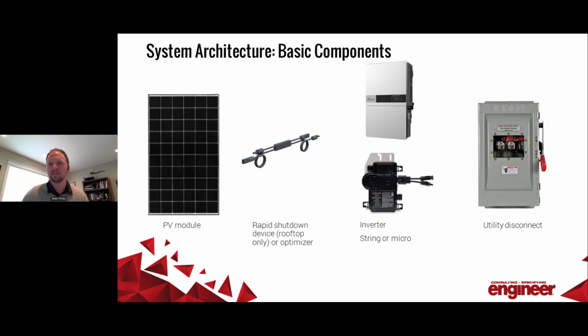The basic pieces of any solar system are shown here. We'll start with our PV modules. We're all probably familiar with those. On any commercial building, we'll probably have hundreds to thousands of those on a rooftop array or carports, whatever. To the right of that is a rapid shutdown device, or maybe an optimizer. For rooftop solar arrays, we need to comply with some rapid shutdown codes. And so we'll generally have one of these for every 1 to 2 modules on the rooftop. And they use a communication protocol in the inverter to contain the electricity within the module, or within that device, basically, and the system gets shut down for fireman protection.